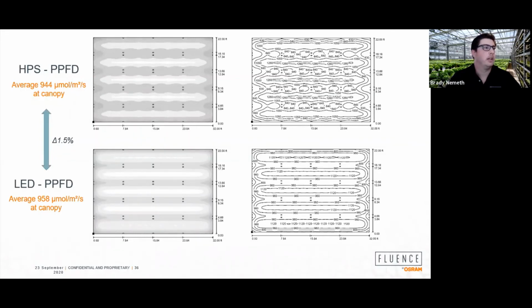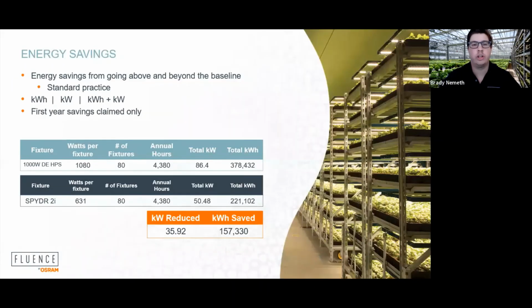Next slide. So looking at this example, we'll say it was a flowering room based on the fixtures that were in there. 12 hours a day, more or less running all year, for annual hours of 4,380. Again, 40 per tier, so 80 total in each room. You're just basically running through those numbers, and in a room of that size, you'd be looking at kWh savings of just shy of 160,000.